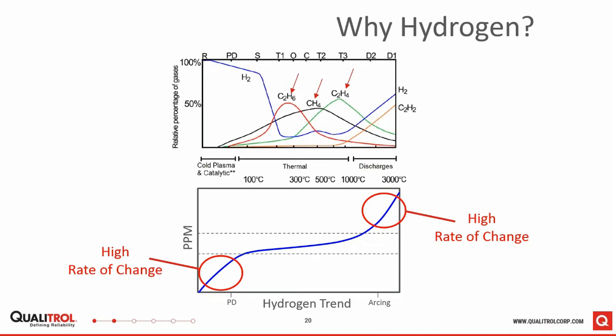As you get hotter and hotter, once you start creating acetylene, all the other gases are dropping off, the methane, ethane, and ethylene, and you're left with acetylene, which is C2H2. You only have one hydrogen molecule there, so when you're producing acetylene, you also produce a lot of hydrogen. The graph at the bottom of the screen shows that at lower temperatures, such as in the PD range, you see a significant increase in hydrogen. And as you get into the middle range, your hydrogen is still increasing.